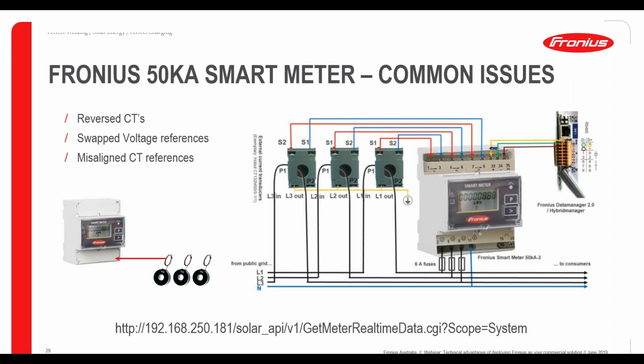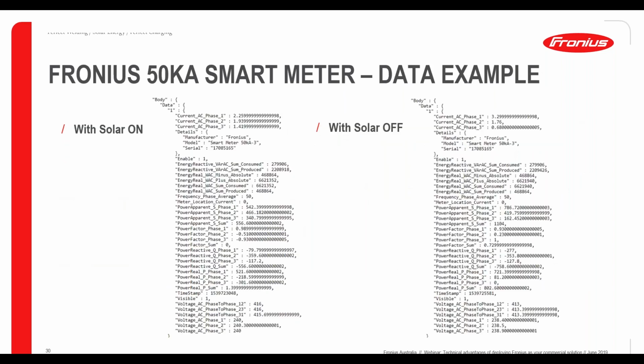If you just have a look through the details here, it's very easy to troubleshoot the per-phase scenario of how your site looks. What we recommend is to turn your solar off and then measure the actual power flow per phase, shown as real power P. If you're seeing a negative value there, that's a telltale sign the CT is wired in reverse. Also, be cautious of the power factor per phase. If your loads typically don't have very low power factors, but you start seeing numbers in the likes of 0.1 or 0.2, that's a telltale sign that the voltage reference is coming from a different phase. So that can be played around with to get the correct measurement.